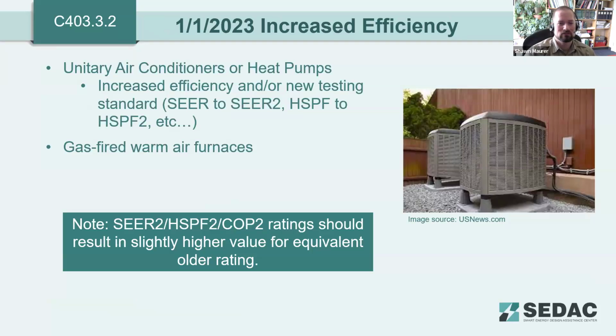Efficiency is increasing. So something that many of you may have seen in industry already is that the SEER, HSPF, and COP ratings are being updated to SEER 2, HSPF 2, and COP 2. If you have a unit that has a SEER rating, there are ways to convert that to SEER 2, and the result should be a slightly higher value for the equivalent older rating. What these changes are accounting for are slightly different estimates of loading throughout the season, trying to account for part load efficiency of these systems. And then gas-fired warm air furnaces have also had their efficiencies increased in these tables. So even though the SEER ratings are updating to SEER 2, HSPF to HSPF 2, they're also increasing the efficiency requirement of those systems in those tables.